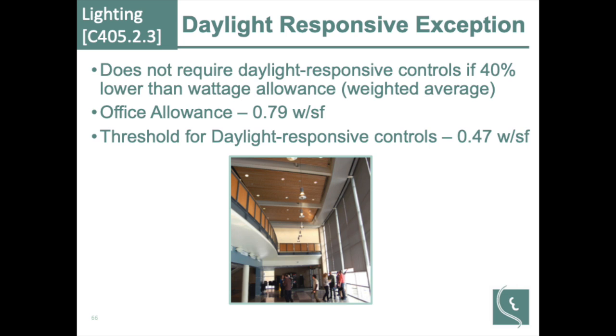But this is my favorite exception. Rarely do I like to call out exceptions in the code. This one by far is a great one to use, and I highly encourage the use of this. And that is for daylight responsive controls, and that is if you are able to reduce your lighting power by 40% of the weighted average area. We'll talk about that in a little bit. If you get below that 40%, you don't have to do daylight harvesting at all.